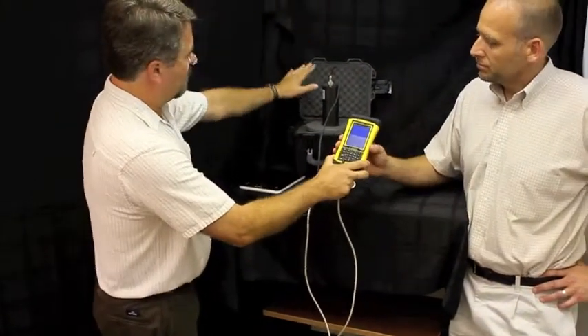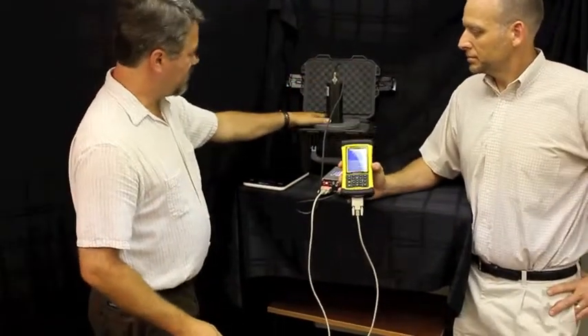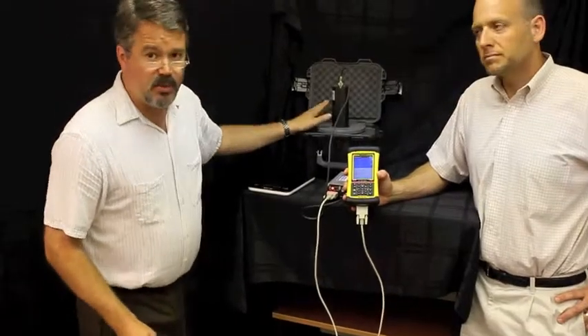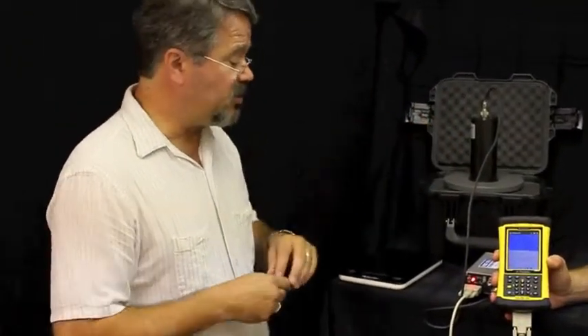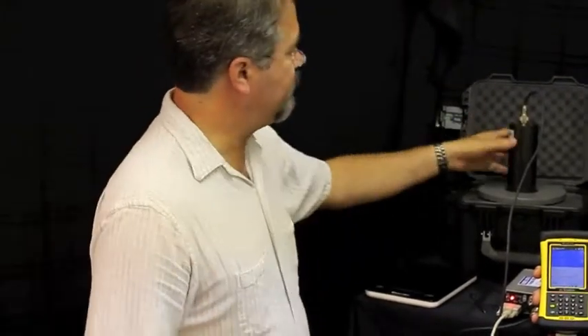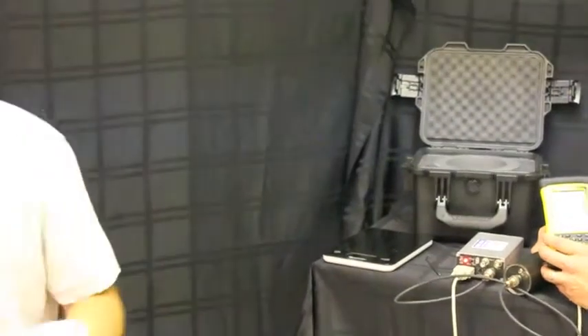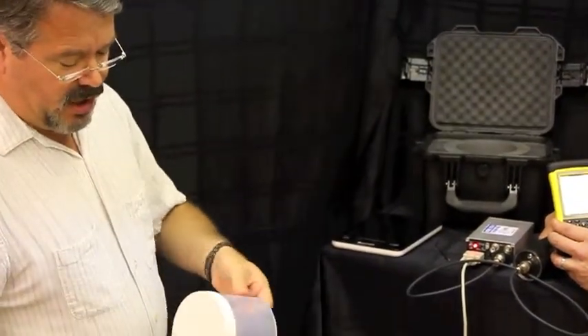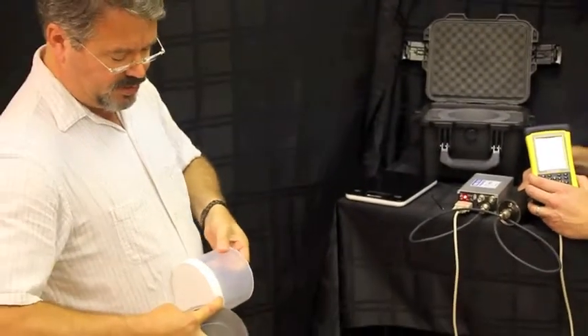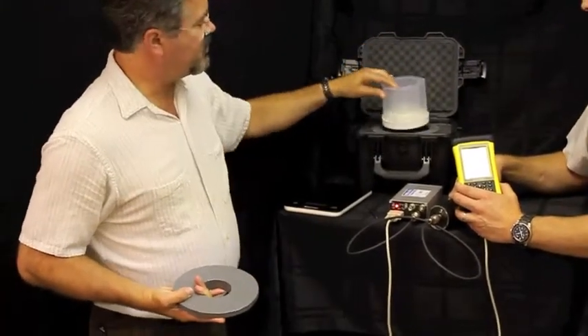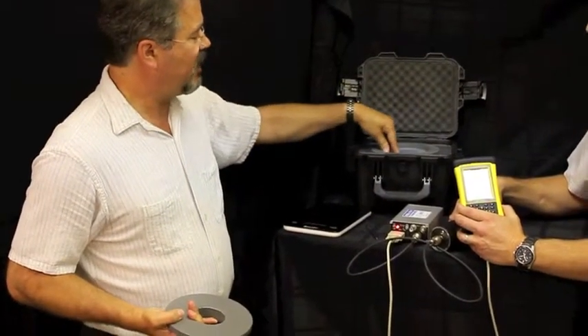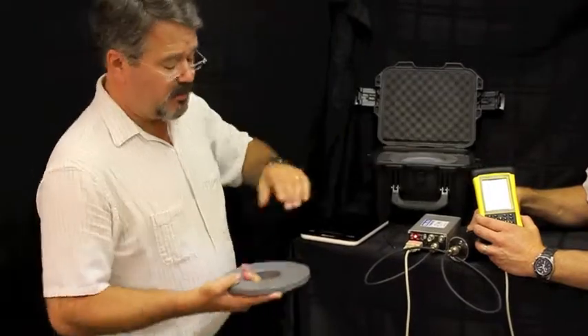After you have stabilized and double-checked your source, the most important thing that you're always going to want to do when you're doing food samples and comparisons, comparing against what? Well, we want to compare against what our background radiation is, so we can identify that and subtract that out of the picture, and then know that all that's left is the activity that we've introduced in the meantime. We would continue, most likely in the field, to be using these Marinelli type beakers. And it's very important that you always perform your samples and activities with the same type of geometry, same type of shape, same type of positioning. So we still will use an empty Marinelli chamber.